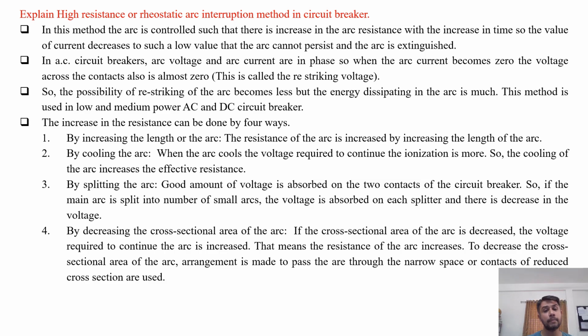By splitting the arc, a good amount of voltage is absorbed on the contacts of the circuit breaker, meaning the moving and fixed contacts. If the main arc is split into a number of small arcs, that is, we cut the main arc into small chunks, the voltage is absorbed on each splitter. The last method is by decreasing the cross-sectional area of the arc. If the cross-sectional area of the arc is decreased, the voltage required to continue the arc is increased, which means the resistance of the arc increases. To decrease the cross-sectional area, arrangement is made to pass the arc through a narrow space or contacts. So this is how the high resistance or rheostatic arc interruption method works in the circuit breaker.